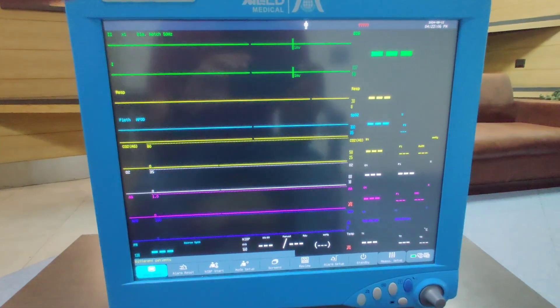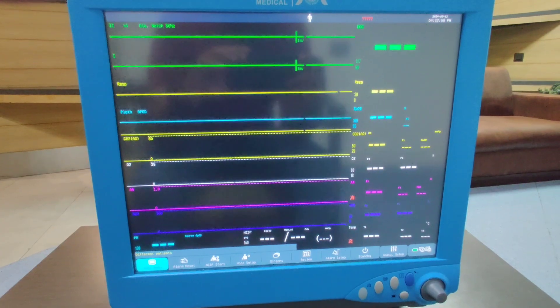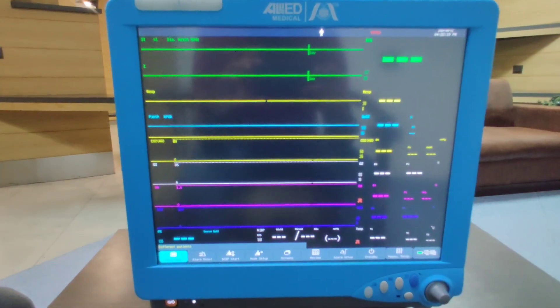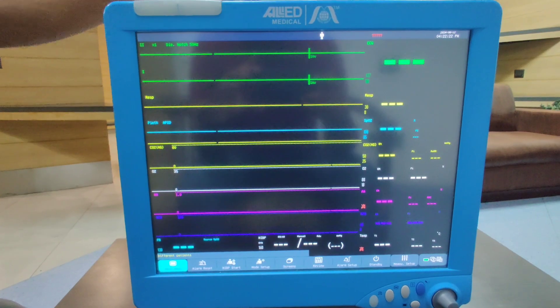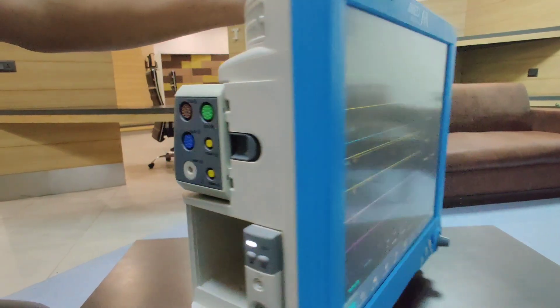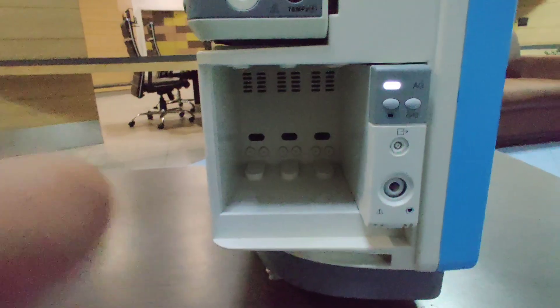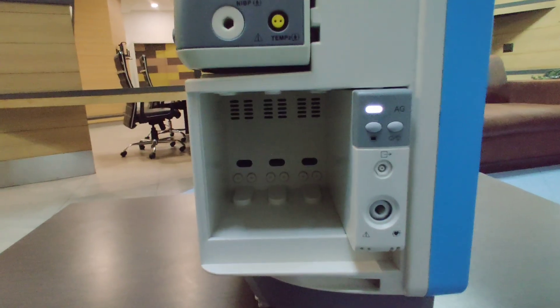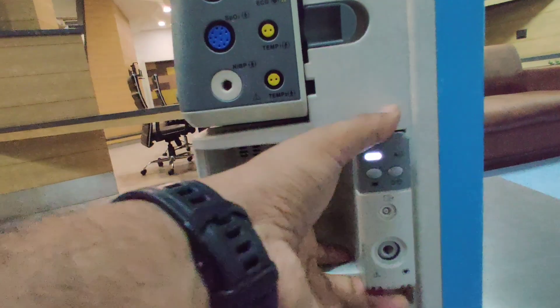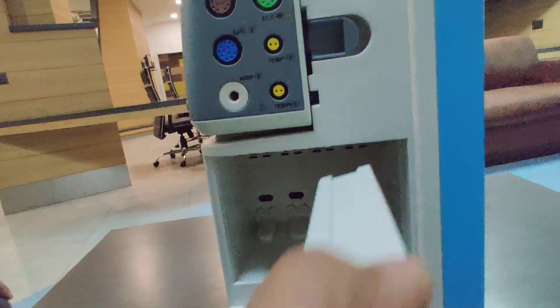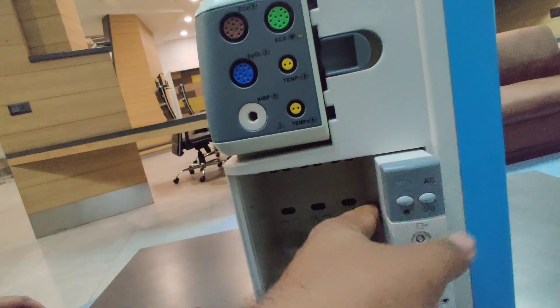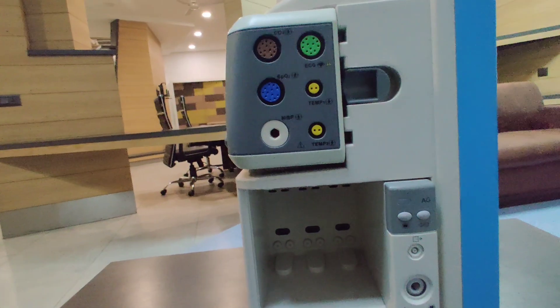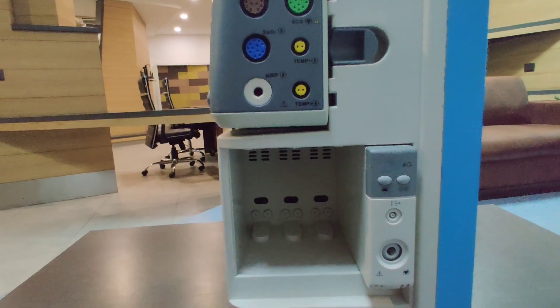Discussing the upgradable parameters, on the left side we have the place where you can mount any of the parameter modules. These are plug-and-play kind of cassettes, so as soon as you plug this on the monitor, that parameter will get activated. We have three more places for putting upgradable or advanced parameters.